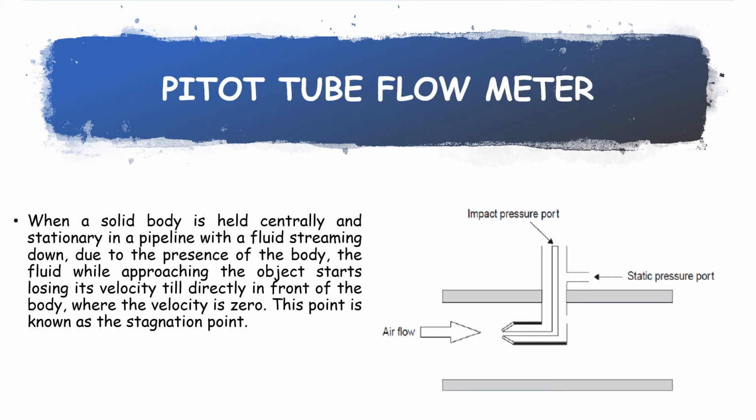Here we can say that a common industrial type Pitot tube consists of a cylindrical probe inserted into the air stream. The fluid flow velocity at the upstream face of the probe is reduced substantially to zero. Velocity head is converted to impact pressure, which is sensed through a small hole in the upstream face of the probe.